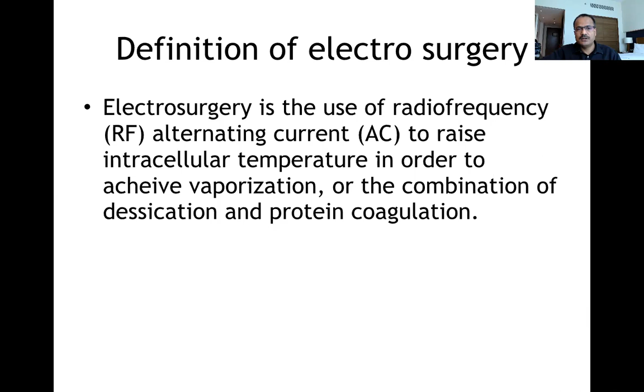So the definition ends: use of radio frequency, alternating type of current to raise the temperature in order to achieve only vaporization, that is cutting, or a combination where you get desiccation and protein coagulation. The carbonization and caramelization are additions. They are not there in the definition. So friends, to summarize one more time, the use of radio frequency alternating current to raise the intracellular temperature so as to achieve desiccation, coagulation, or vaporization is electrosurgery.